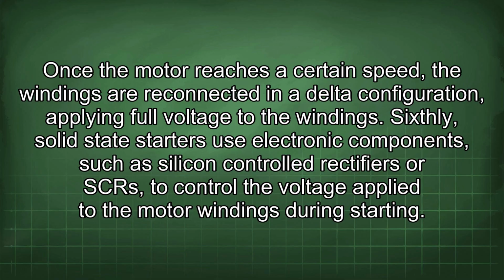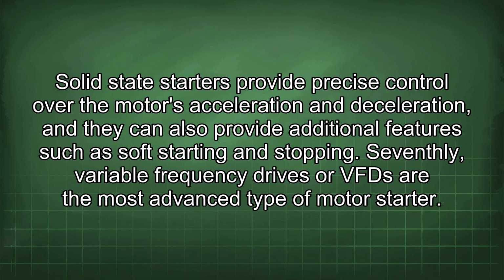Sixthly, solid-state starters use electronic components, such as silicon-controlled rectifiers or SCR, to control the voltage applied to the motor windings during starting. Solid-state starters provide precise control over the motor's acceleration and deceleration, and they can also provide additional features such as soft starting and stopping.